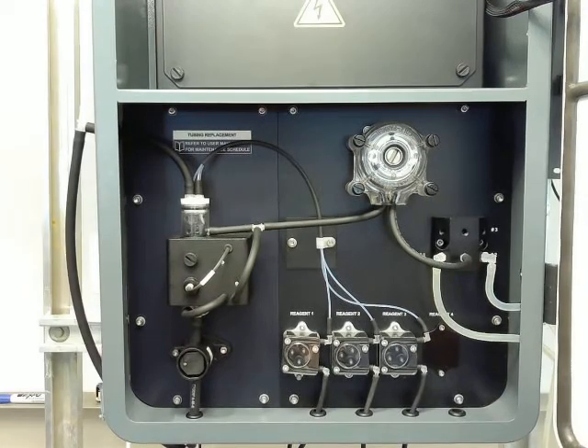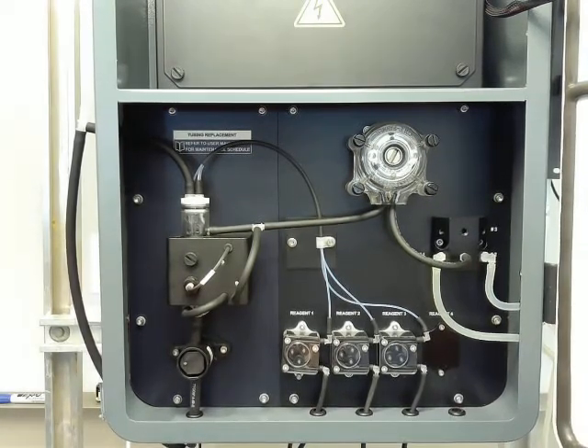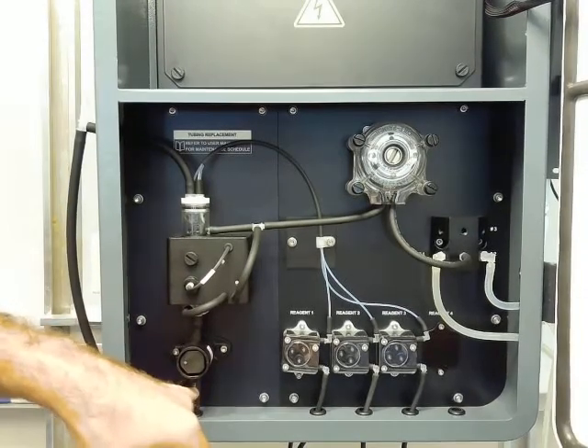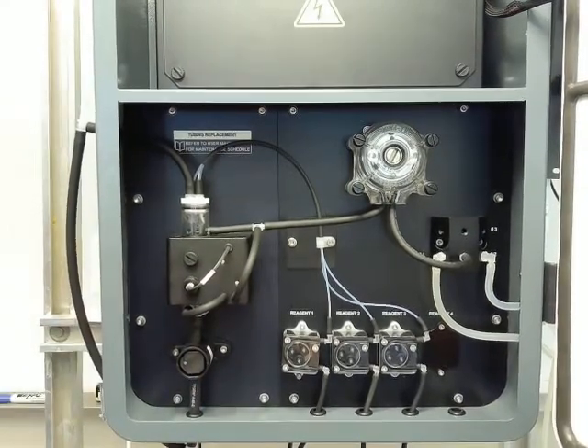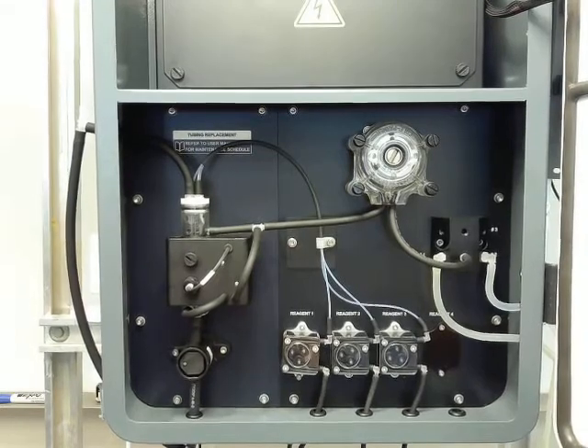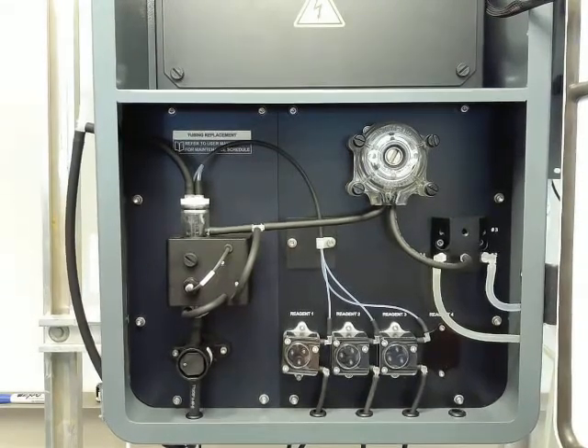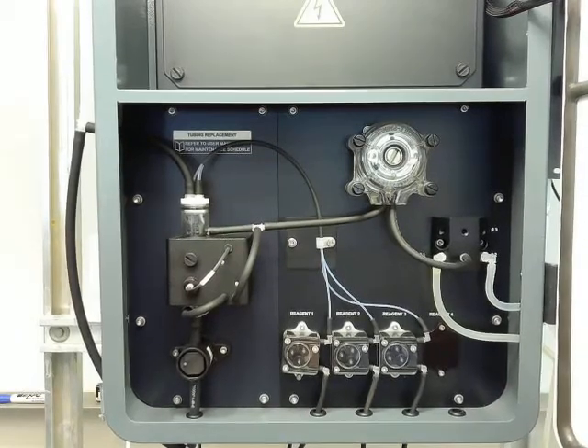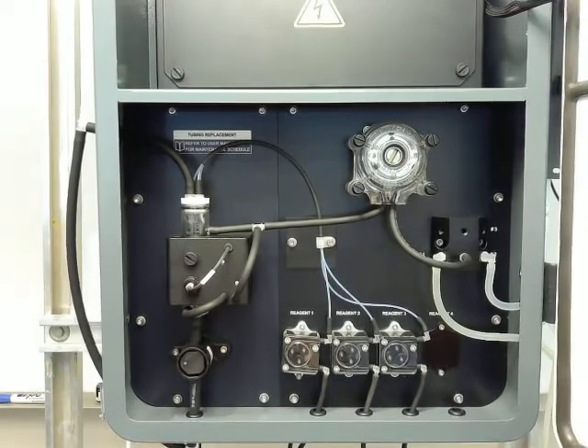So the first one that I'll go through is the flow cell drain tubing replacement. So that's this one down here. To take that one off, the best way to do it is really take out the flow cell itself, and that way you can clean out the flow cell at the same time. It's always a good idea to do that.